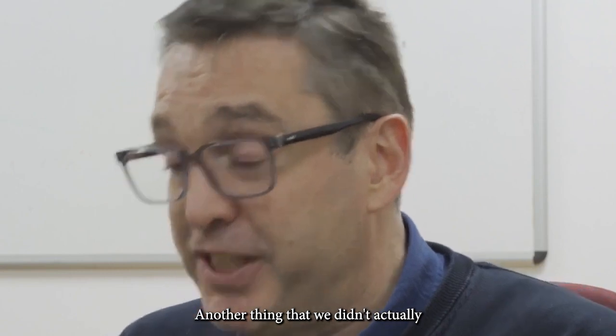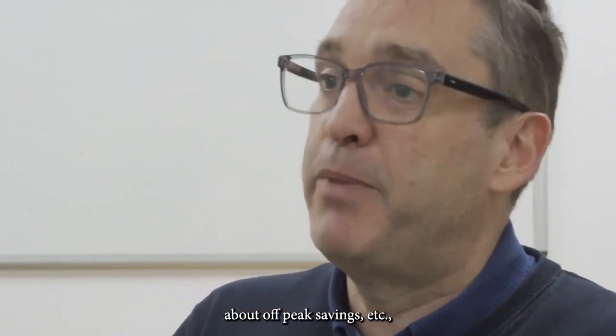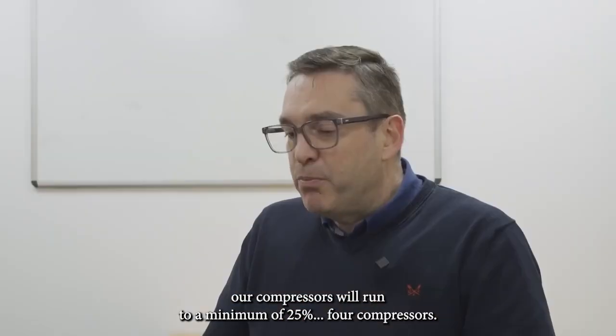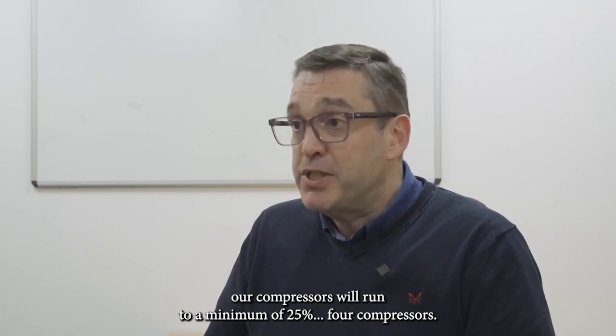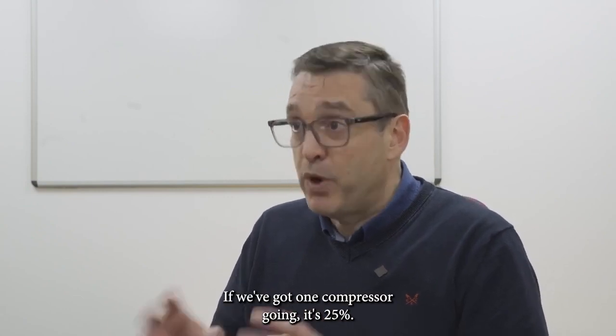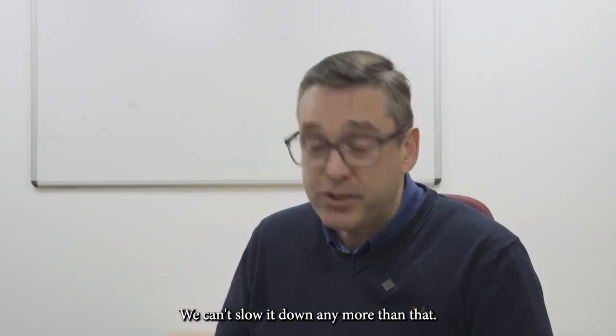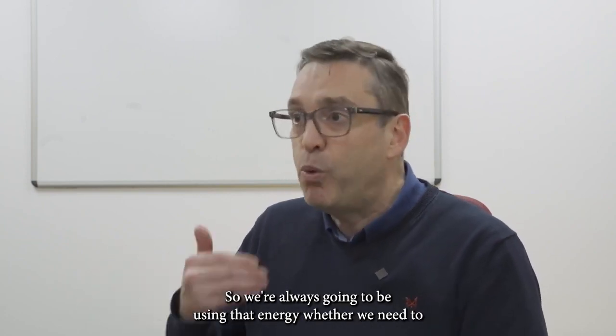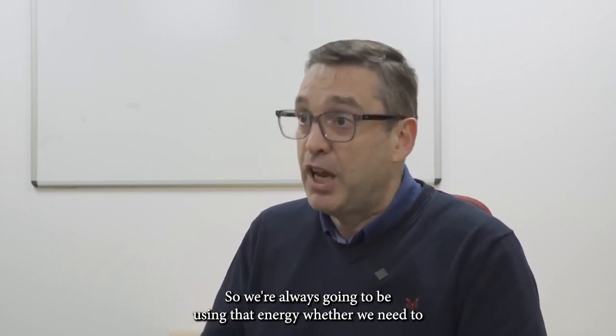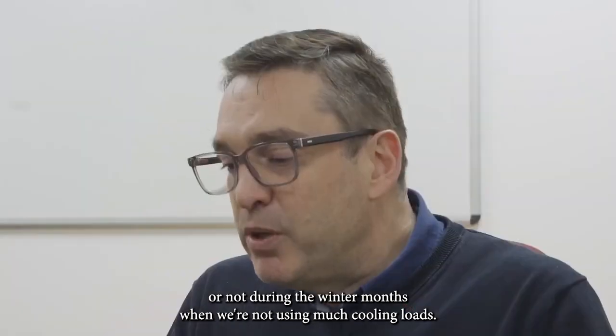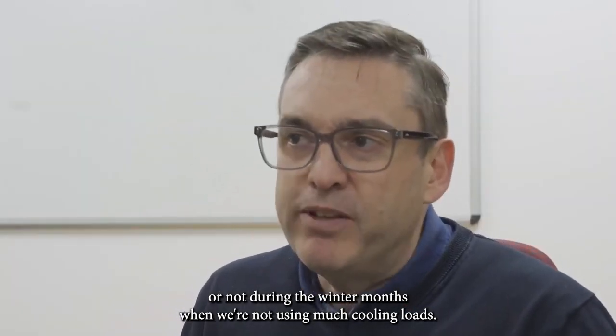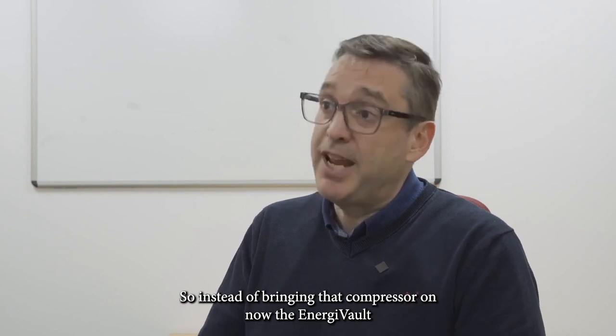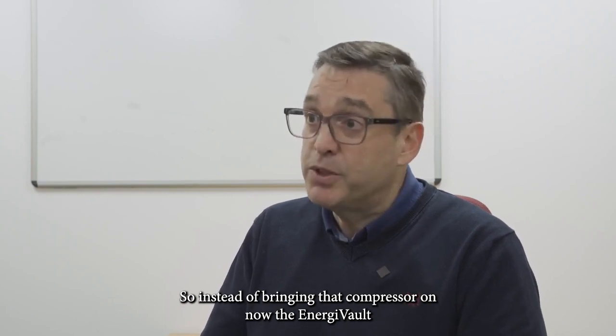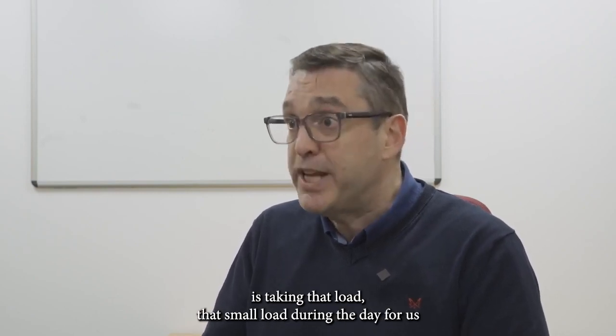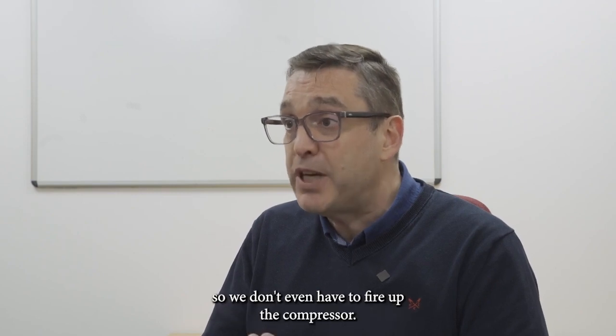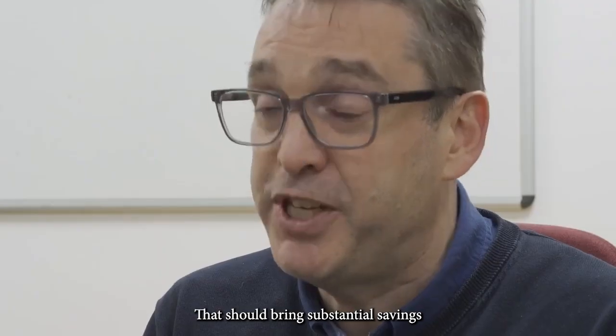Another thing we didn't consider when it went in, because we were looking at off-peak savings, is that our compressors will run to a minimum of 25%. With 4 compressors, if we've got 1 compressor going, that's 25%, and we can't slow it down any more than that. So we're always going to be using that energy, whether we need to or not. During the winter months, when we're not using much cooling load, instead of bringing that compressor on, the EnergiVault is taking that small load during the day for us, so we don't even have to fire up the compressor. That should bring substantial savings.